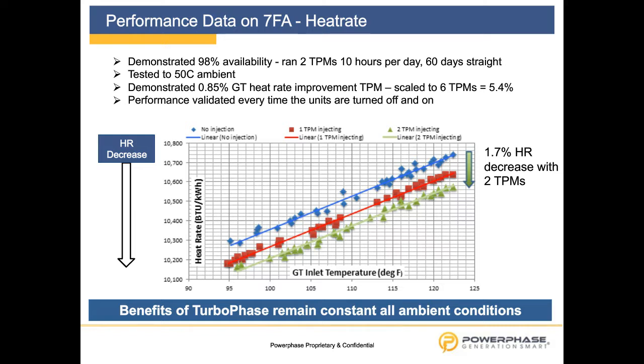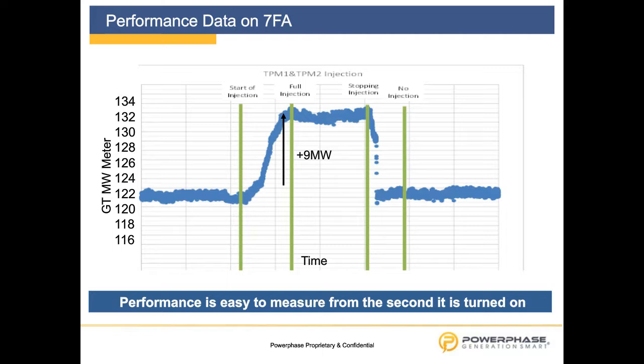I have here, of the same gas turbine, a similar picture. We have the base load of the gas turbine, 122 megawatt. From the moment we switch the Turbophase module on, you see the immediate impact, which makes it really easy for performance tests and very straightforward in terms of what megawatt we are adding and what efficiency we are adding. It is important to mention that these output and efficiency values are guaranteed values that we commercially fix with any end customer. This is about real-time data.